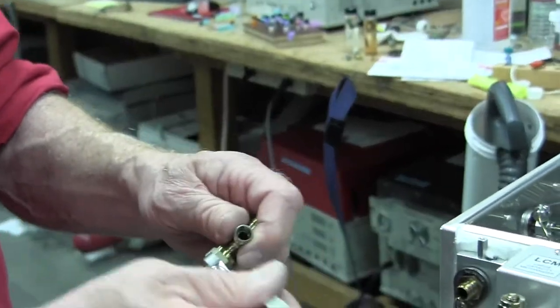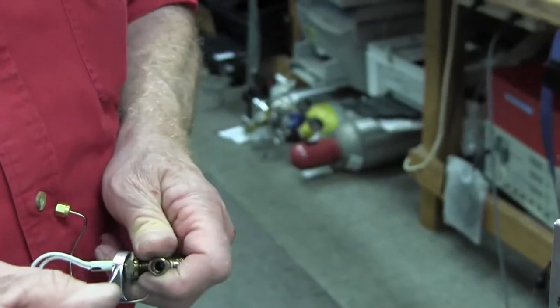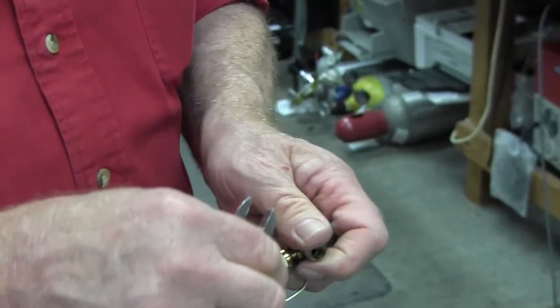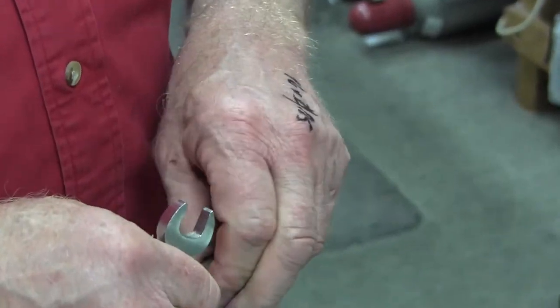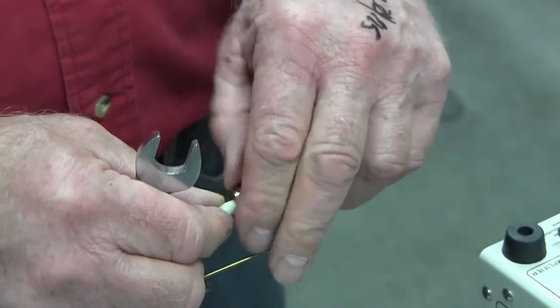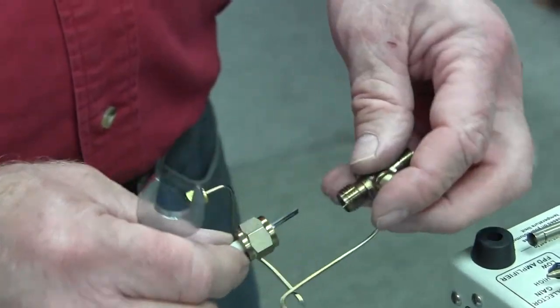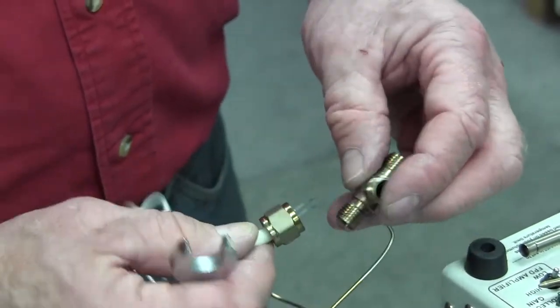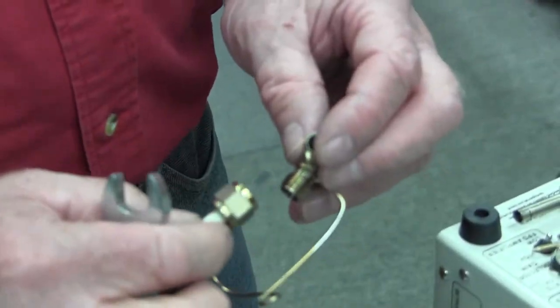You can see much more clearly inside. I'm going to remove this, this is called the igniter. You have to be a little careful when you remove this not to hold the igniter while you turn the nut, because if you just twist, you can twist this against something that might damage it, so you have to be careful to hold it.